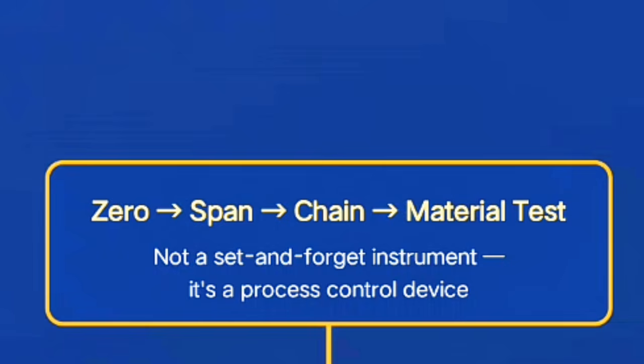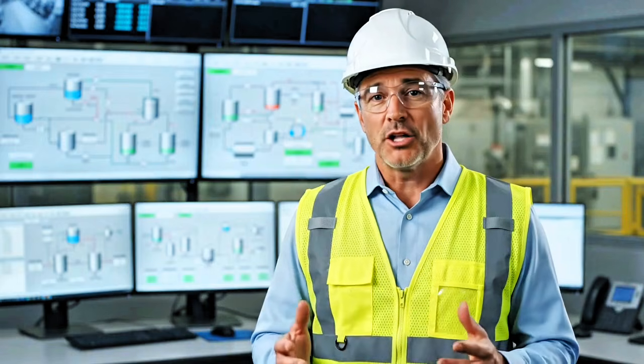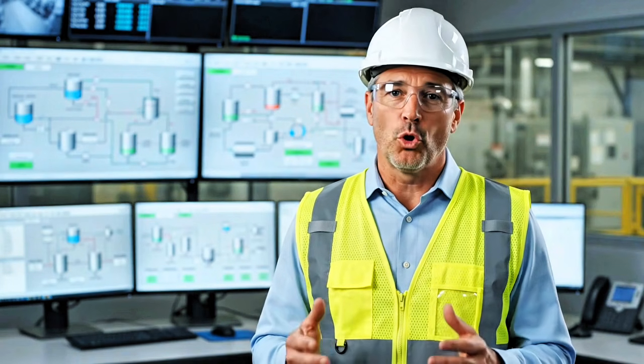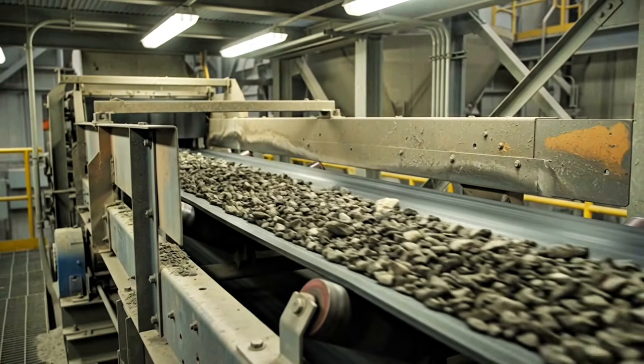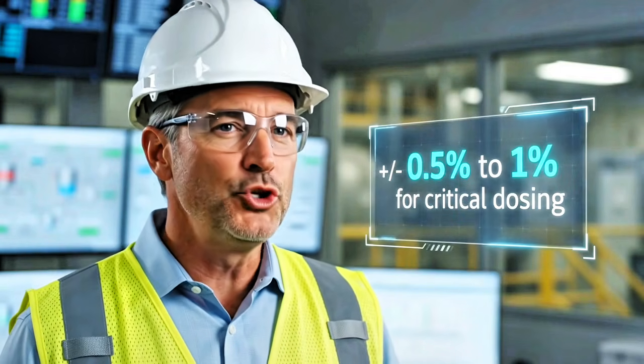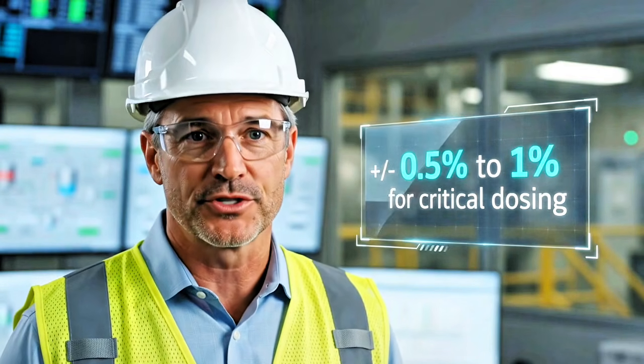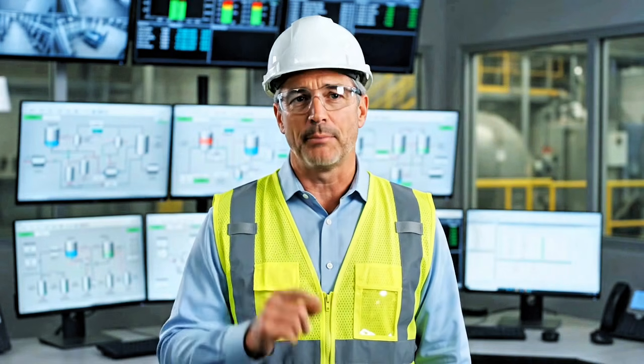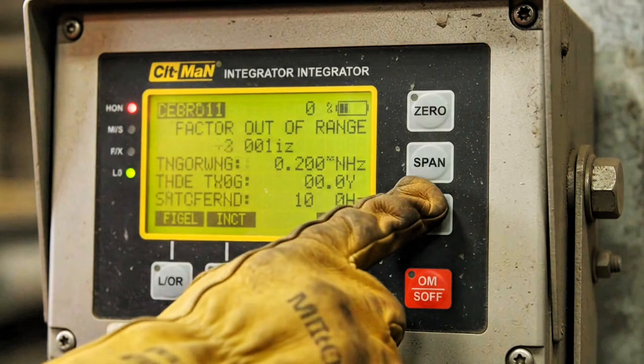Track your calibration results over time, not just pass or fail. If successive span calibrations are drifting in the same direction, say, always needing a slightly larger correction factor each quarter, that's telling you something mechanical is progressively wearing, and you should investigate before it becomes a bigger problem, not just keep correcting for it indefinitely. For tolerance, most cement plant feeders should hold within plus or minus 0.5% to 1% for critical dosing applications like kiln fuel, and you can accept a slightly wider tolerance, maybe 1 to 2%, for less critical bulk material transfer. Check what your specific process actually requires, don't just apply a blanket number.